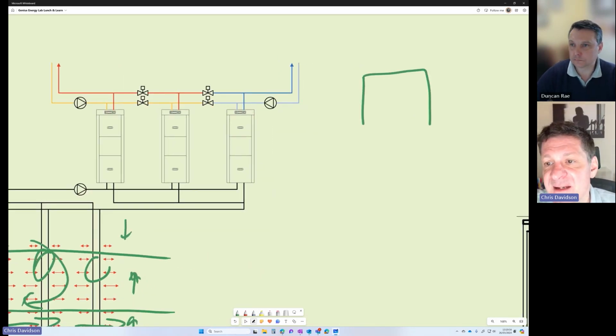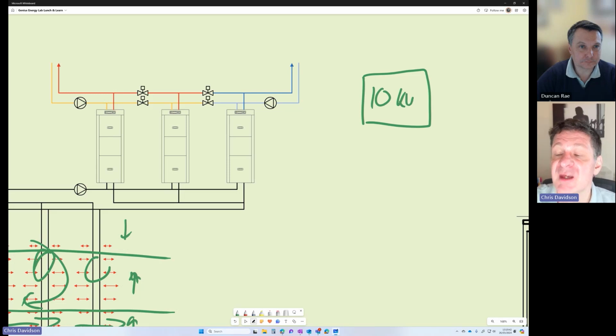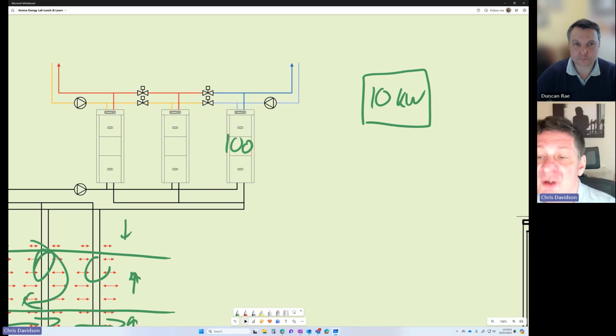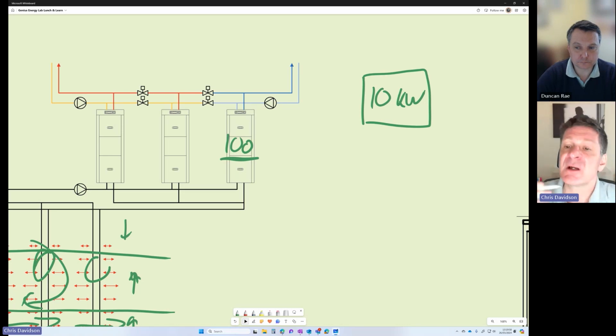Let's say we've got a 10 kilowatt... That's helpful, the fire alarm hopefully isn't about to go off. Let's say we've got a little 10 kilowatt server room load here. So it's just cooling all year round. And let's say we've got those 100 kilowatt heat pumps here. Let's say we're in the dead of winter. All these heat pumps are heating. And so to satisfy that 10 kilowatt cooling load, we've now got to bring on that 100 kilowatt compressor and deliver that 10 kilowatt cooling load.